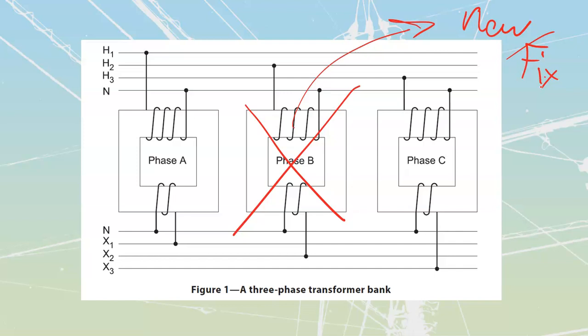So we will see these setups, but as I said, usually the banks are used in large industrial settings, particularly when dealing with higher voltage values, over the 600 volt range or the 750 volt range we have inside our Canadian electrical code. Okay, that's it for that.